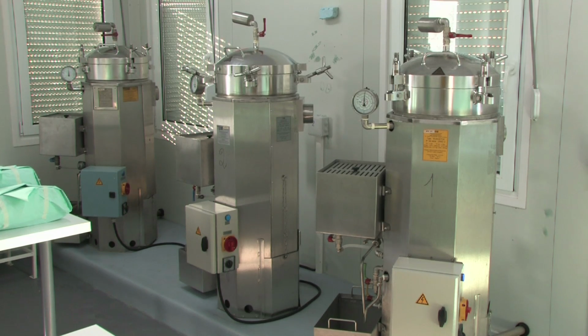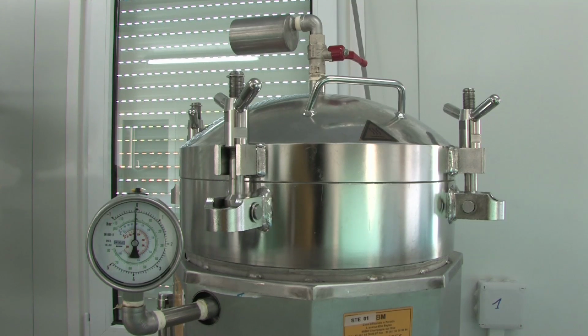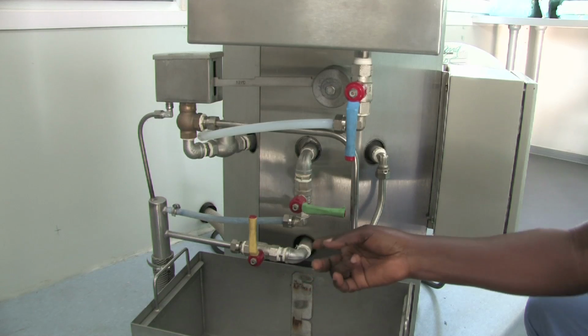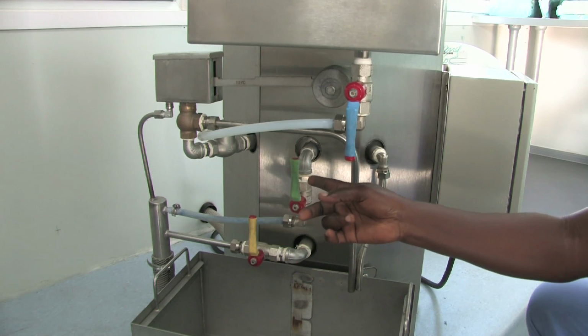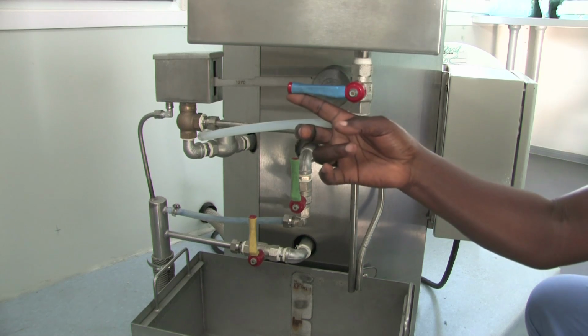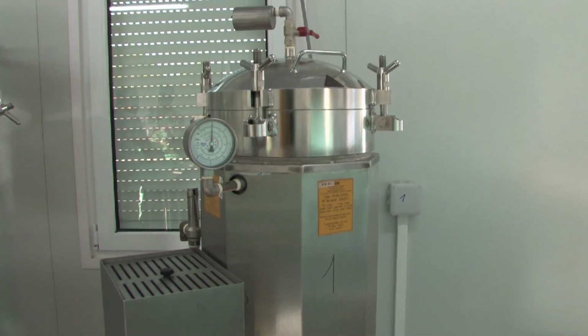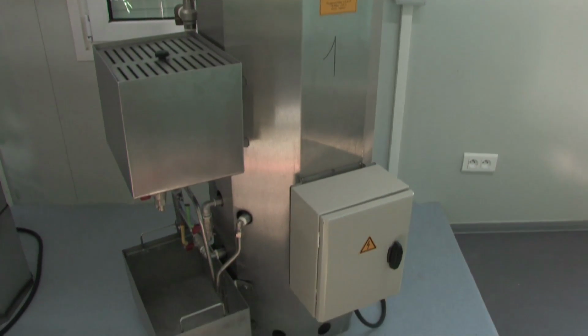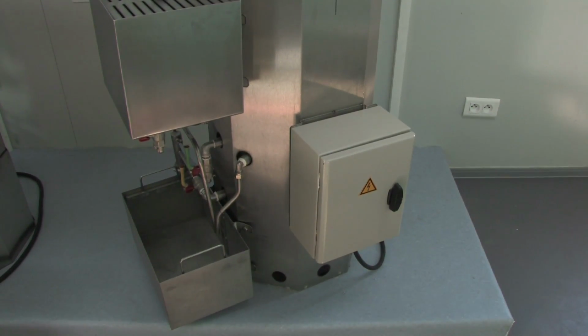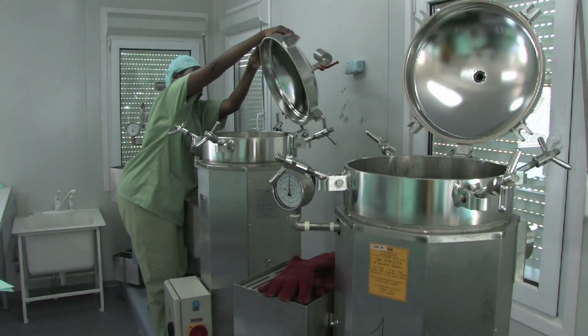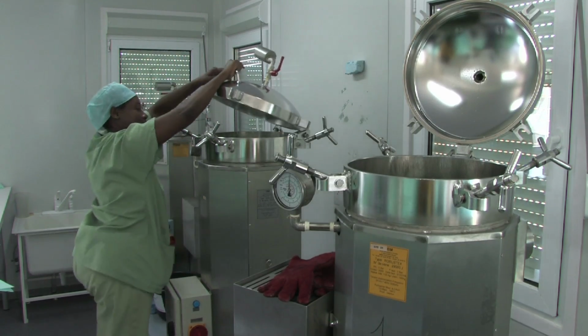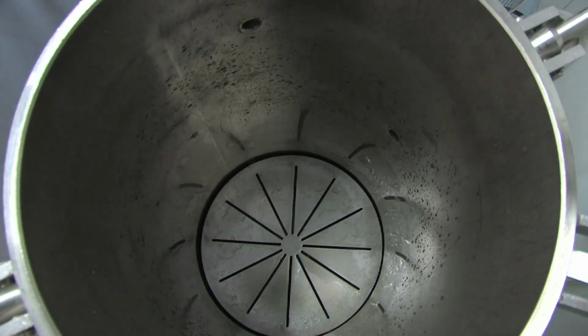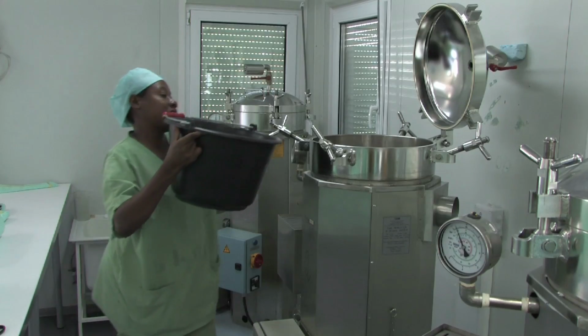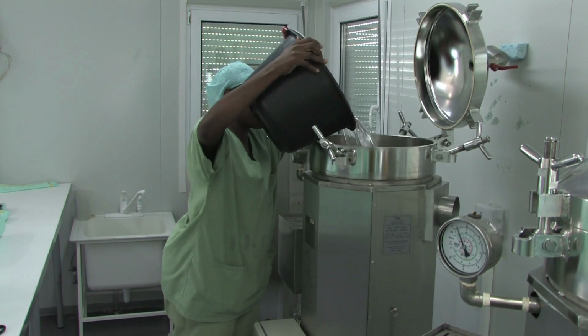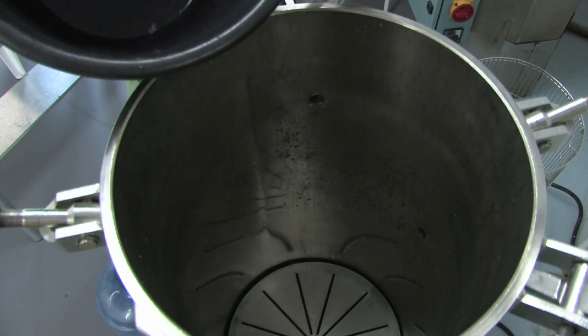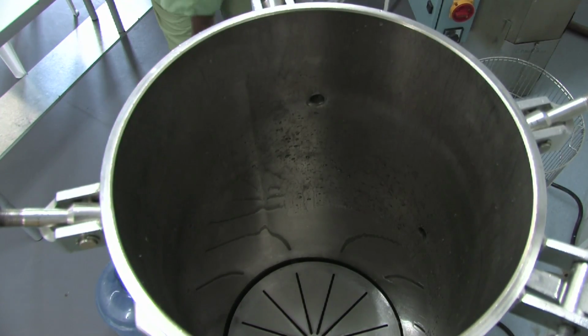The TBM-90 is a small volume steam sterilizer. This 90-litre vertical autoclave uses electricity to convert water into steam. While a gas burner can also be used as the energy source, this requires a longer cycle and fills the room air with soot. The electrical heating element is at the bottom of the chamber, under a protective plate, and must be completely covered with water when the autoclave is operated using electricity.